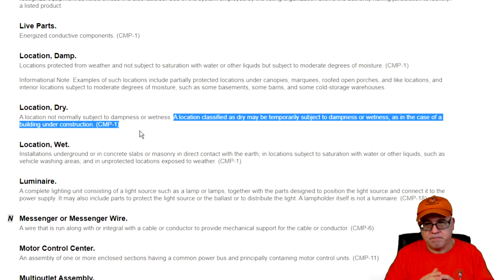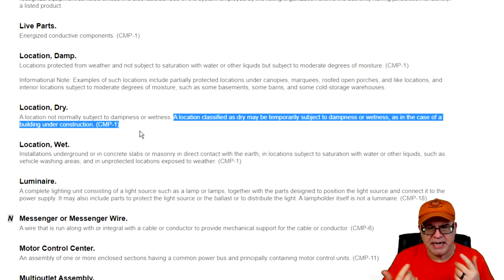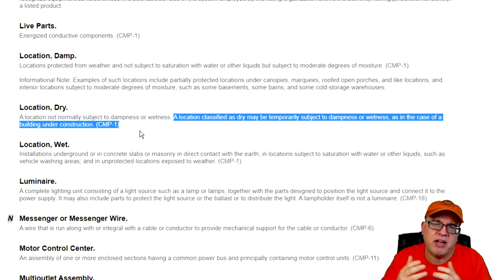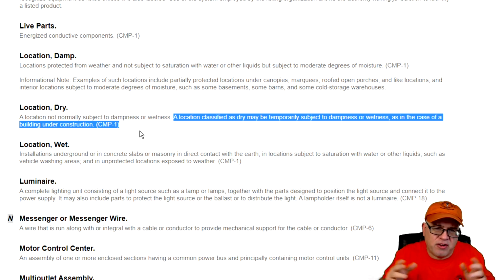So what does this mean? Okay, so I'm framing up a building. It's a wood frame, make it easy. And I'm pulling non-metallic sheath cable in it, which incidentally is a product that's rated for dry location. So is MC, by the way, if you don't put a PVC jacket covering on it. So we're just talking dry location. And all of a sudden a storm comes in. Now, if moisture or some wetness or dampness gets on the cable assembly, that didn't remove the fact that it's still a dry location. Because remember, the wood framing members all got wet as well. They're not going to rip those out.